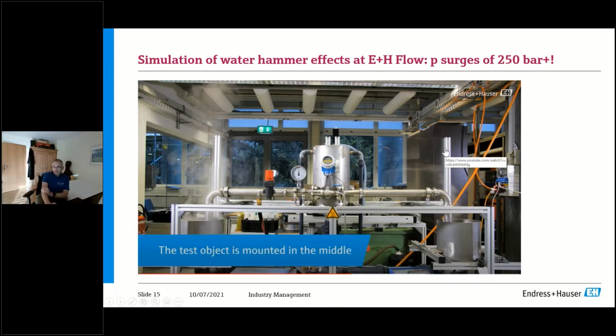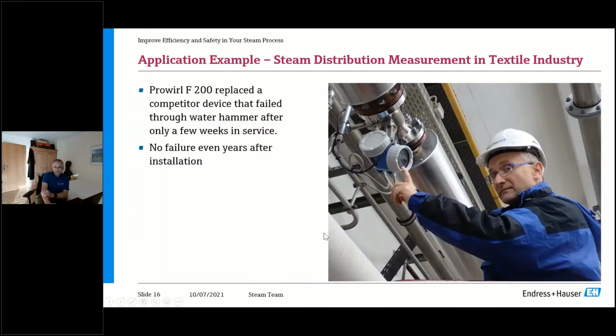Meanwhile, we have a lot of cases where our meters also replaced competitor devices like competitor Vortex meters. Here, this is a case where we replaced a mechanical device, a mechanical spring-loaded orifice plate, they call that. And that failed immediately after one single water hammer. And they replaced that using our Prowirl F200, and they didn't have a single failure ever since. In refineries, we have replaced an entire series of competitor makers' products that kept failing on a regular basis, and they haven't had a single failure ever since. So this is the beauty here.